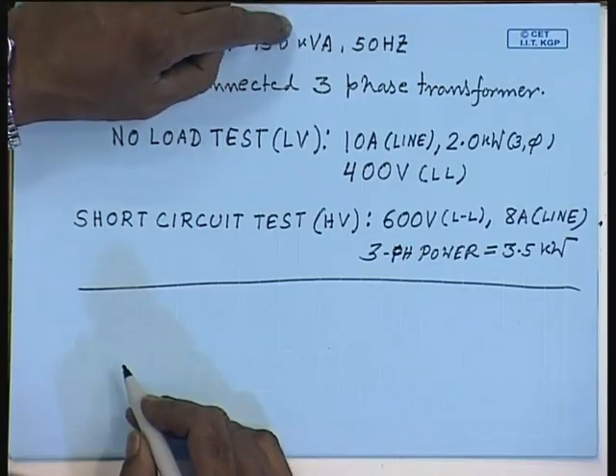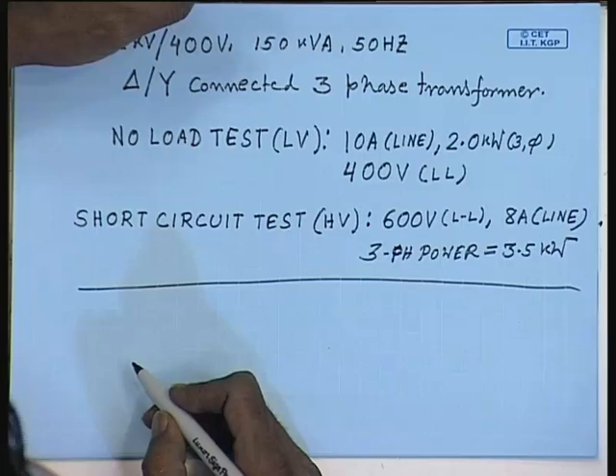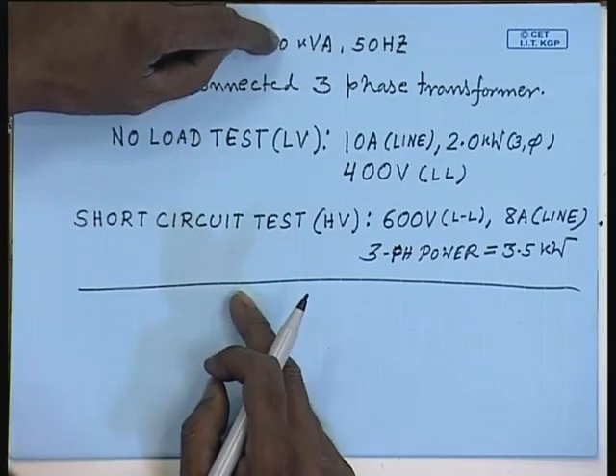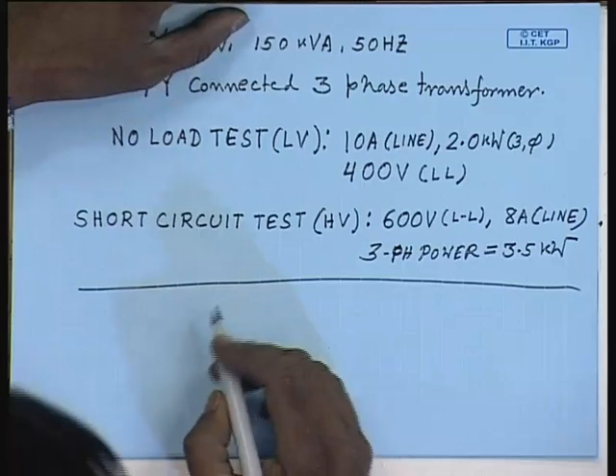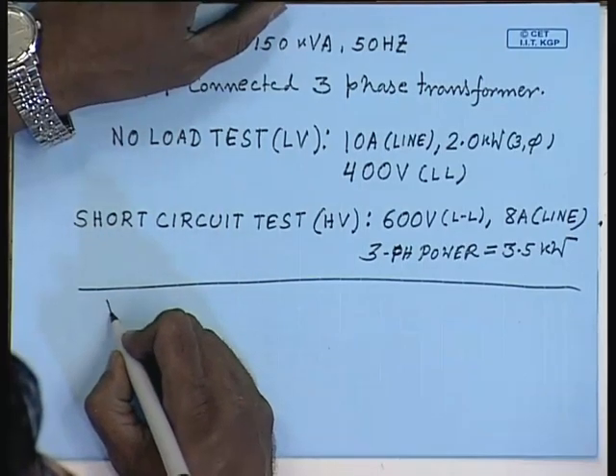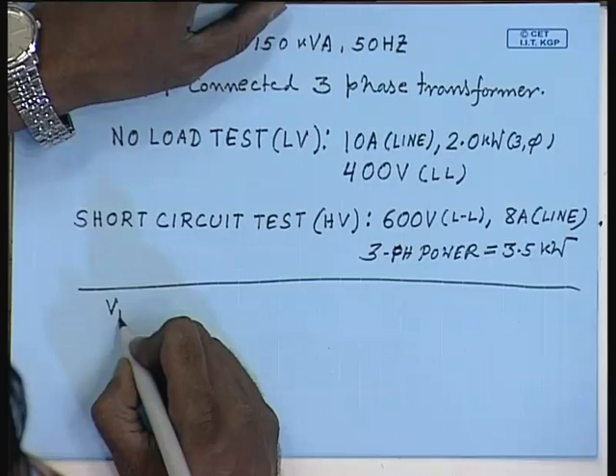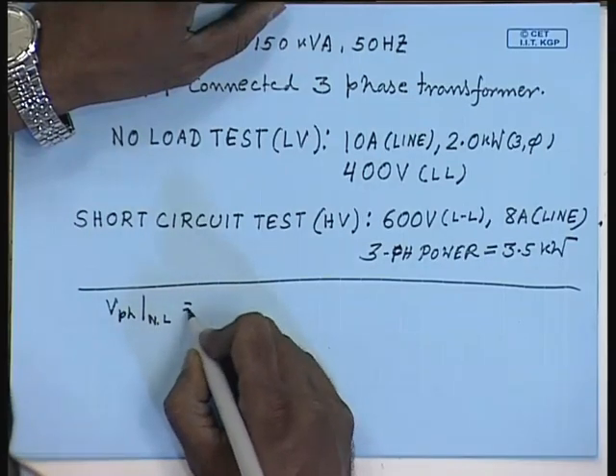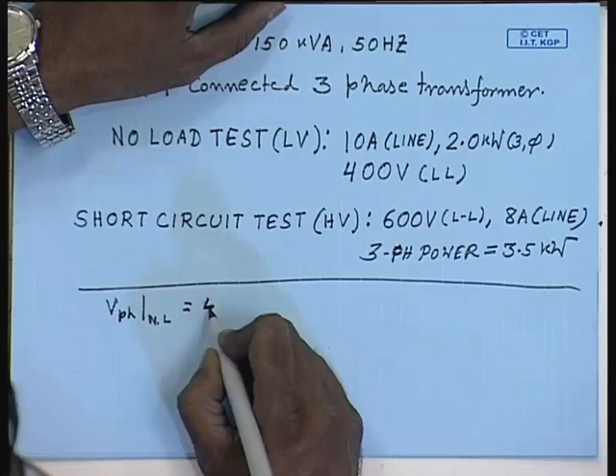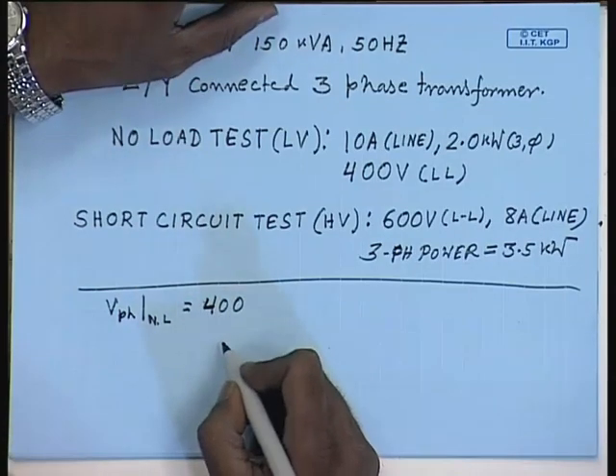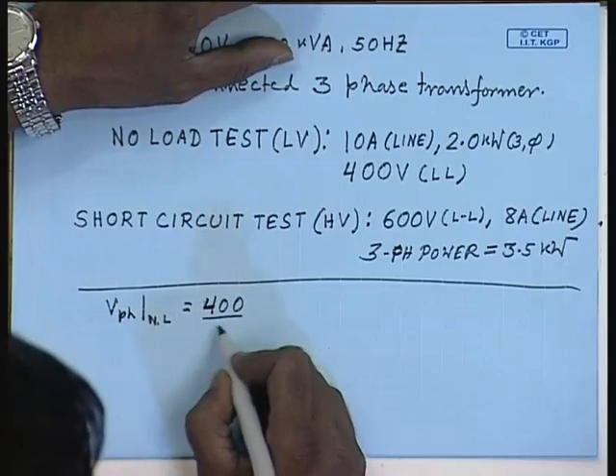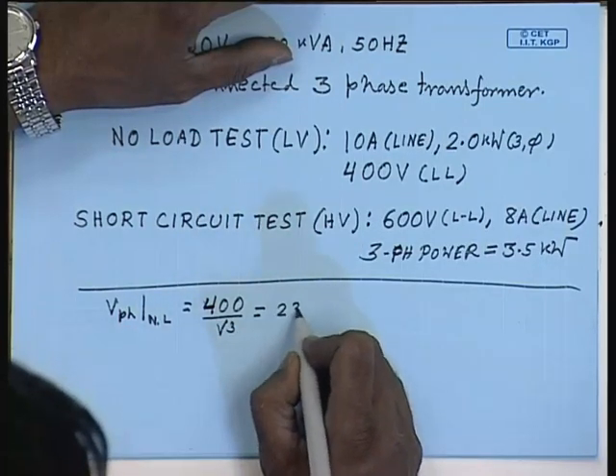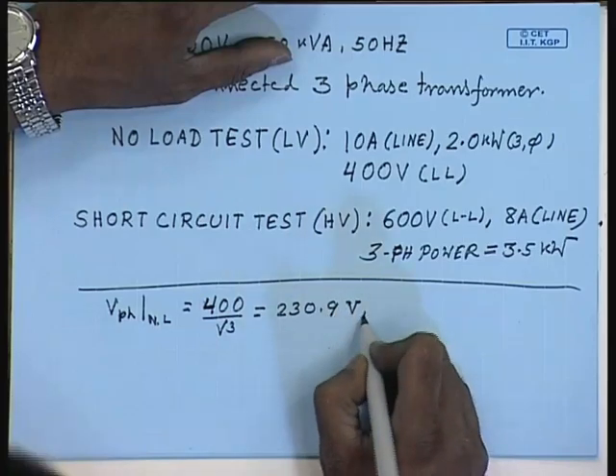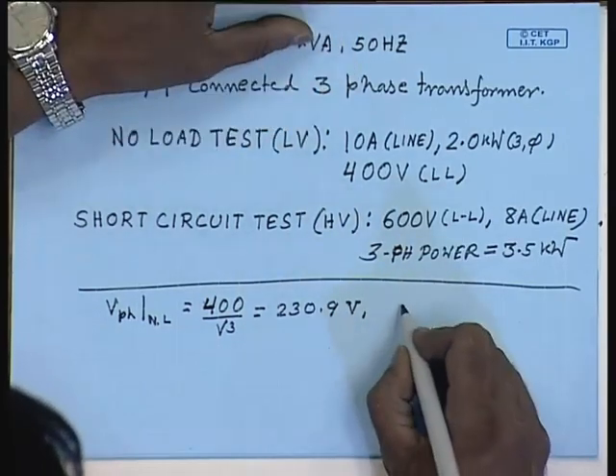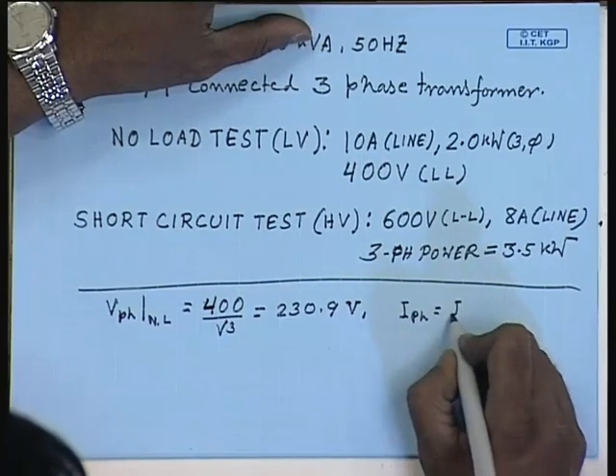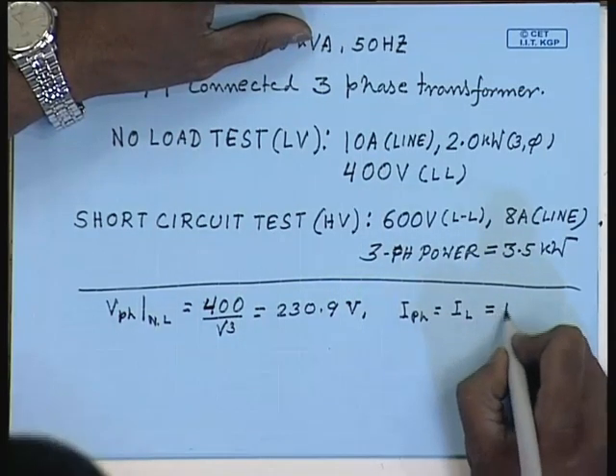So, no load test is performed on the low voltage side, which is star connected. So, phase voltage is equal to 400 by root 3 equal to 230.9 volts, and phase current equal to line current equal to 10 amperes.